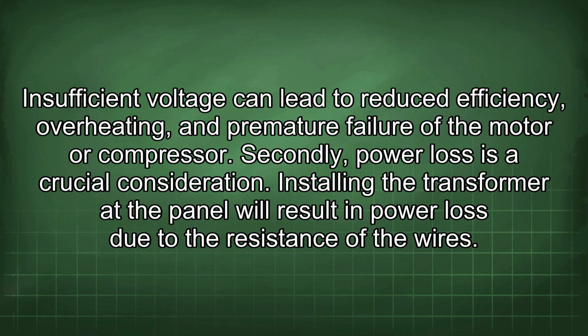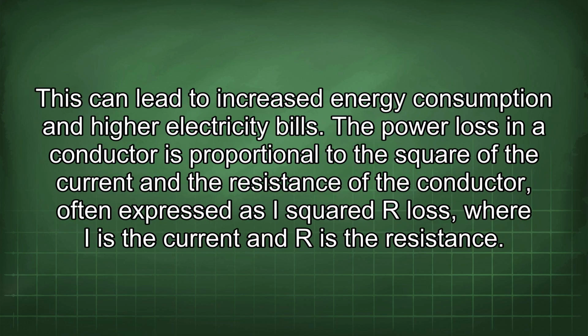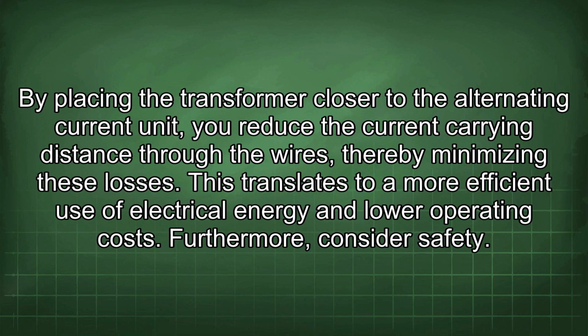Secondly, power loss is a crucial consideration. Installing the transformer at the panel will result in power loss due to the resistance of the wires. This can lead to increased energy consumption and higher electricity bills. The power loss in a conductor is proportional to the square of the current and the resistance of the conductor, often expressed as I squared R loss, where I is the current and R is the resistance. By placing the transformer closer to the alternating current unit, you reduce the current carrying distance through the wires, thereby minimizing these losses. This translates to a more efficient use of electrical energy and lower operating costs.